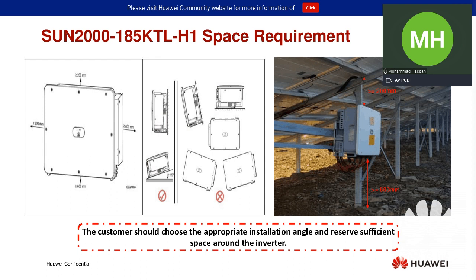Mounting of that inverter: it needs to be mounted straight onto the mounting frame. If you are using rooftops, or where you are laying down the inverter onto the floor, you need to make sure that the inverter is installed at 15 degrees from the plane, so that there will be no problems for the heat dissipating out of the inverter. In the other picture, you can see that we don't recommend installing this 185 KTL in different scenarios or different shapes. We don't recommend installing any of the Huawei SUN2000 inverter series in different shapes onto the wall, because the heat will not be dissipated totally out from the inverters, and it will start creating problems for the installers.